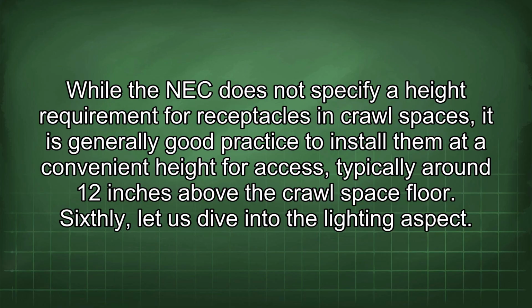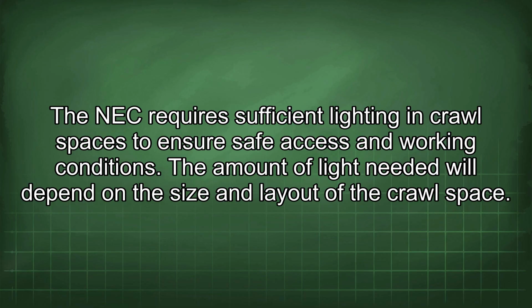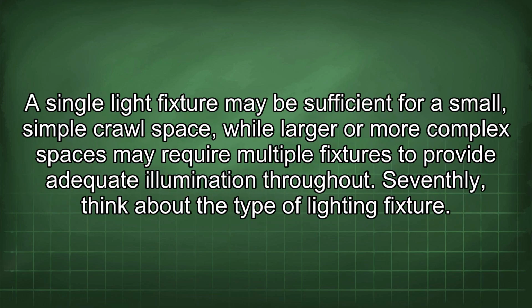Sixthly, let us dive into the lighting aspect. The NEC requires sufficient lighting in crawl spaces to ensure safe access and working conditions. The amount of light needed will depend on the size and layout of the crawl space. A single light fixture may be sufficient for a small, simple crawl space, while larger or more complex spaces may require multiple fixtures to provide adequate illumination throughout.